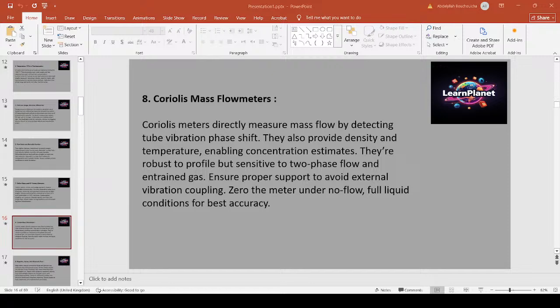Coriolis meters measure mass flow by detecting phase or time shift in vibrated tubes and often report density and temperature too. They excel for direct mass-based custody transfer and concentration measurement, but are sensitive to entrained gas or two-phase flow, which decouple the tube's vibration. Support piping firmly and follow manufacturer's recommendations for straight run and mounting to avoid vibration crosstalk. Always zero the meter with clean liquid, no-flow conditions to establish a baseline. Example: for dosing a chemical by mass to a pipeline, a Coriolis eliminates density compensation math and improves accuracy versus volumetric metering.